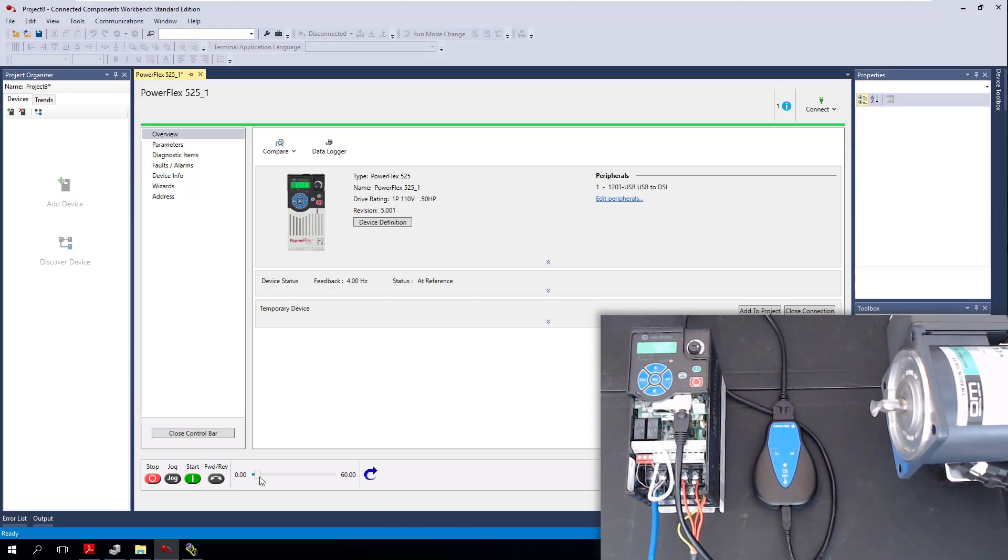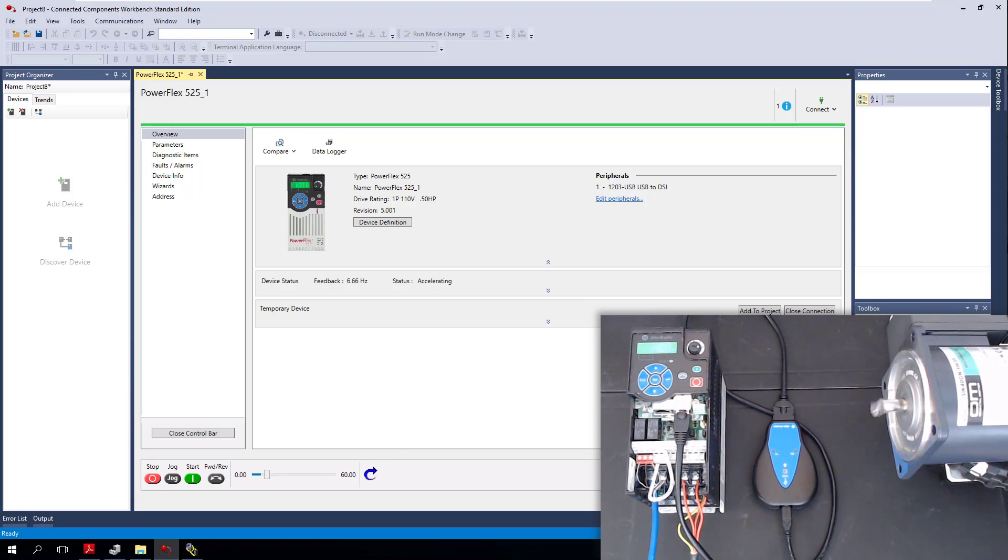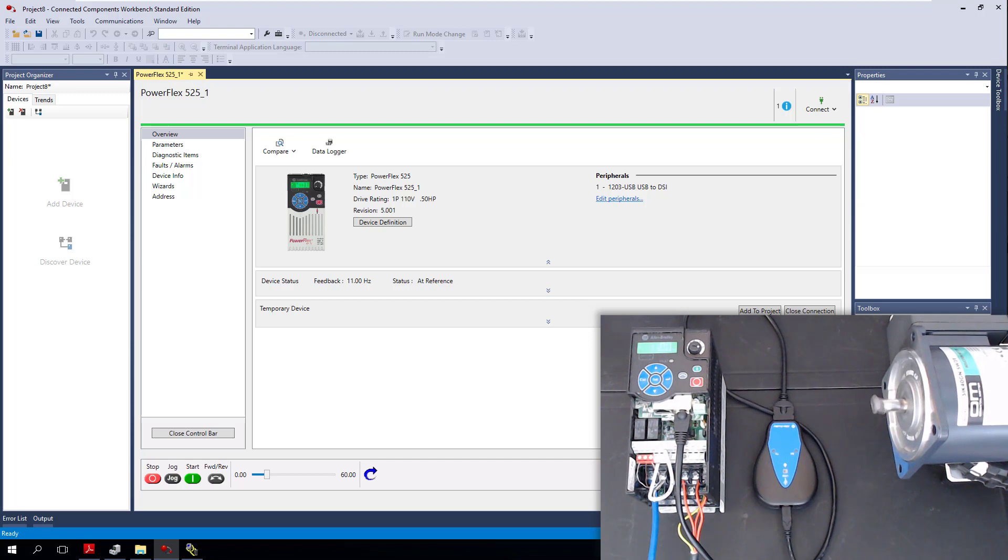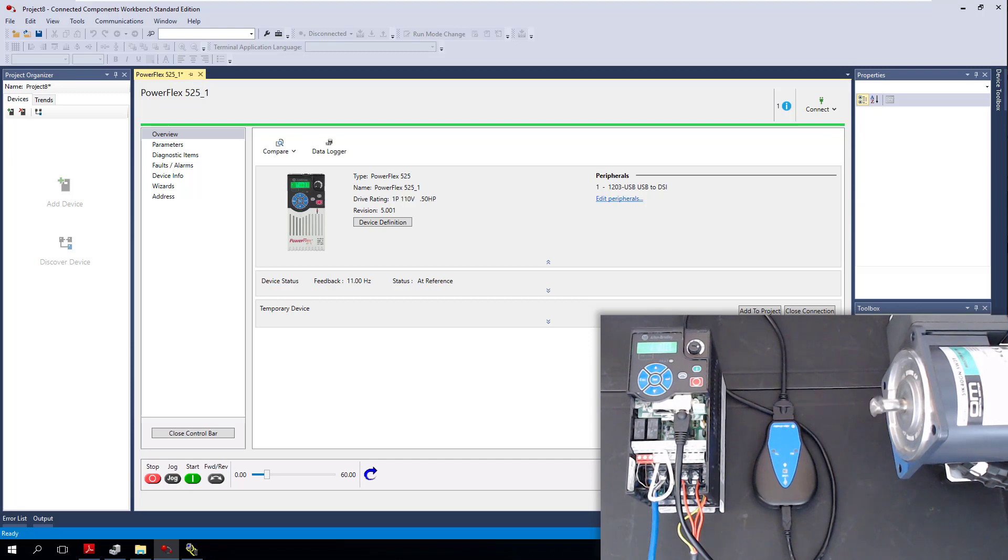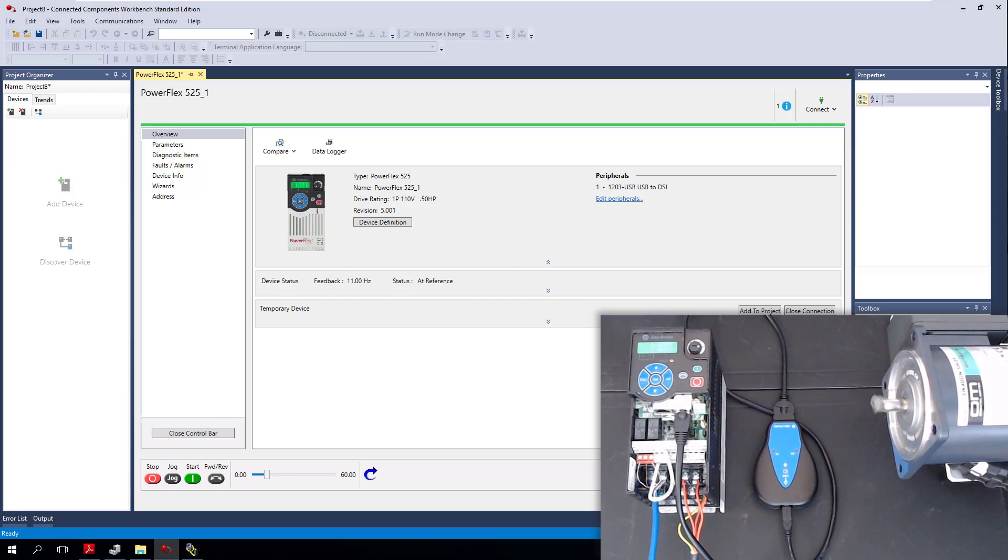Now it's easy to see when that motor is running. I can change the speeds and adjust the speeds as far as that goes. So now that's going at a faster frequency. Keep in mind, this is running a 110 single-phase system to power up the drive, and it's running three-phase out to the actual motor. This is a three-phase 230-volt motor. This is how we're running the motor, and we're talking through our 1203 USB driver, communicating through that. Now it's that simple.